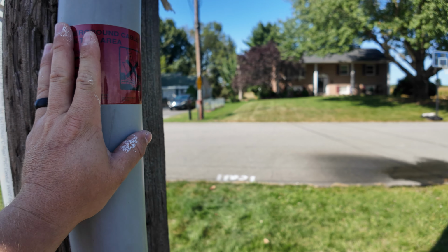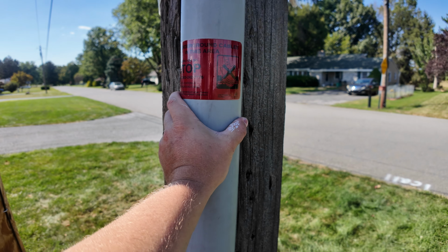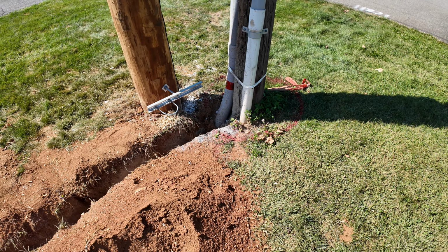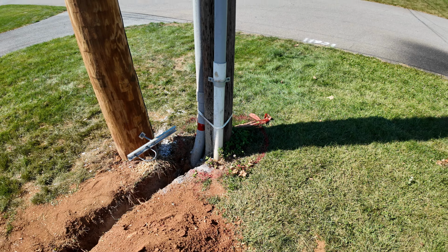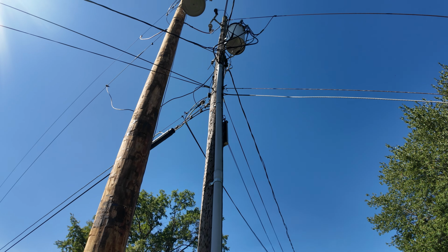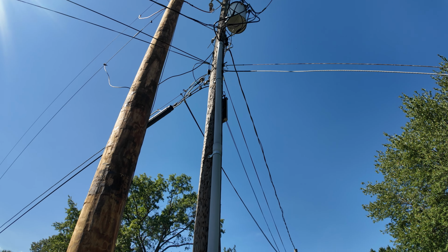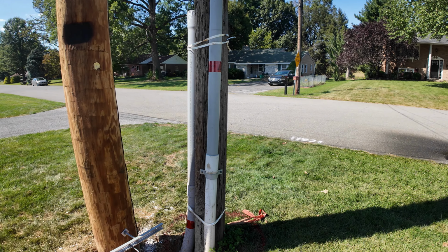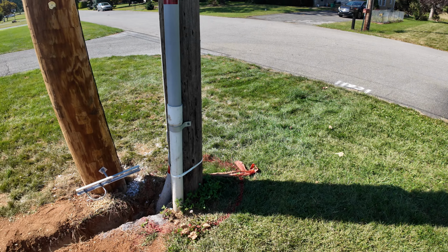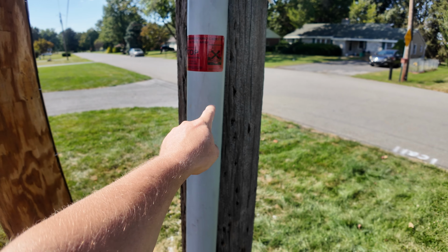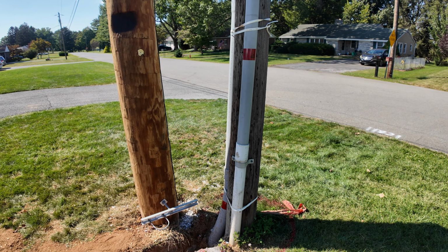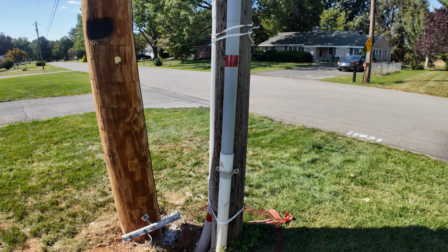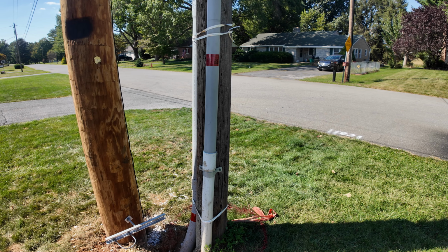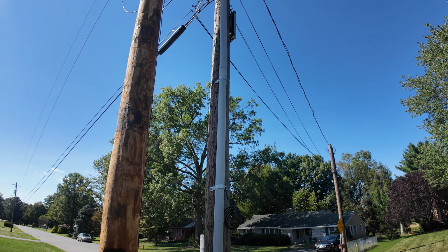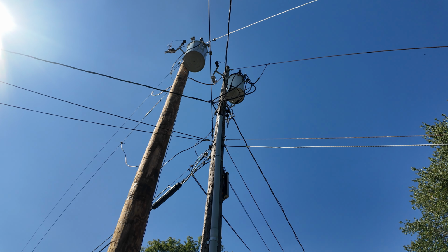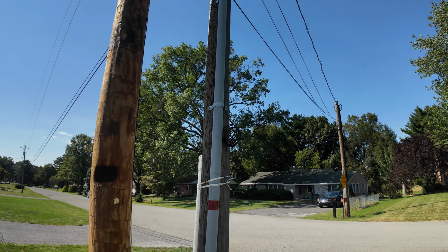Let's talk about our existing service, because that's where the concern is. This one was actually running warm. Talking with the engineer and the lineman supervisor, we found out why. This was put in about a year and a half ago — it's a 350 MCM cable, meant to run 320 amps. It's being maxed out, so it's too small for what we're running. 320 is about 80% of our 400 amp, and I run up to 360-365 amps in my shed. They're okay with that, but it's undersized. Even though the power company originally recommended the 350 MCM, that's normal for a 400 amp, not for a consistent demand like ours.